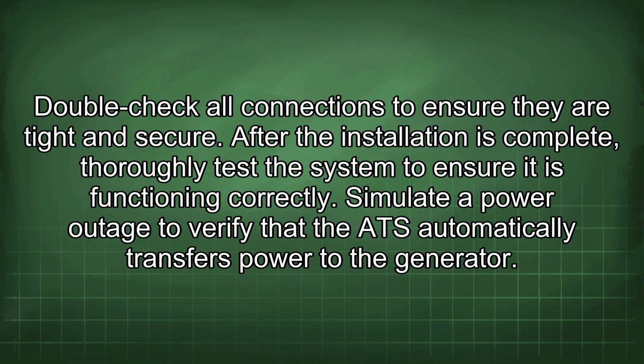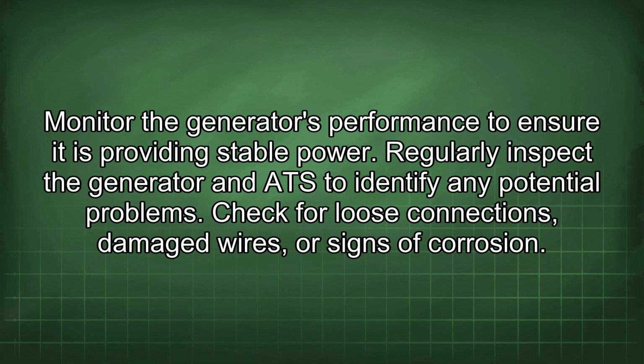After the installation is complete, thoroughly test the system to ensure it is functioning correctly. Simulate a power outage to verify that the ATS automatically transfers power to the generator. Monitor the generator's performance to ensure it is providing stable power.